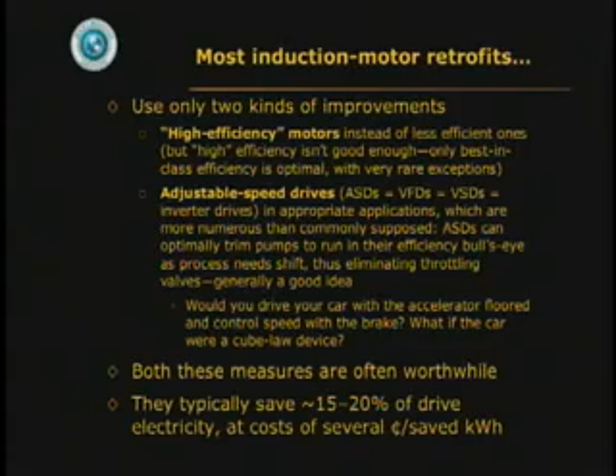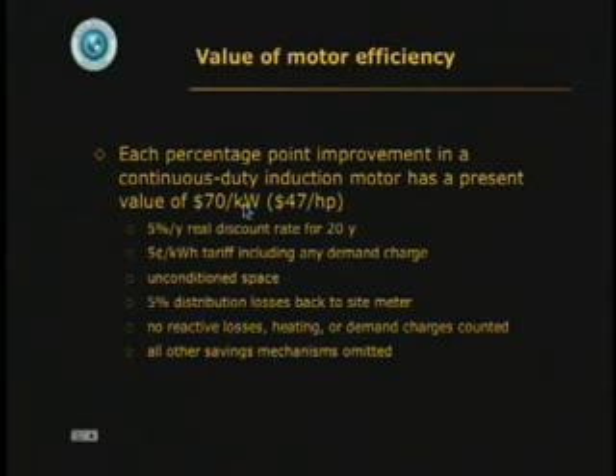And it's worth a lot. Just 1 percentage point improvement in an induction motor running all the time is worth around $70 a kilowatt, present value, at a 5-cent tariff, more here. And it's worth a lot in practice. Here's a typical chip fab where we looked at about 1/3 of the motors, and for those for which we could actually read the nameplate, we found the red X's represented where the motors were, compared with the white dots, which were all the motors of that general type on the US market in 1996. Notice best in class minus red is a big gap, averaging 6.8 percentage points. And that was a pretty typical plant that was about 15 years old.